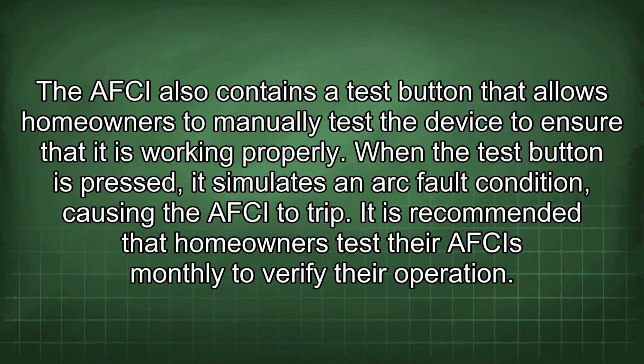The AFCI also contains a test button that allows homeowners to manually test the device to ensure that it is working properly. When the test button is pressed, it simulates an arc fault condition, causing the AFCI to trip. It is recommended that homeowners test their AFCIs monthly to verify their operation.